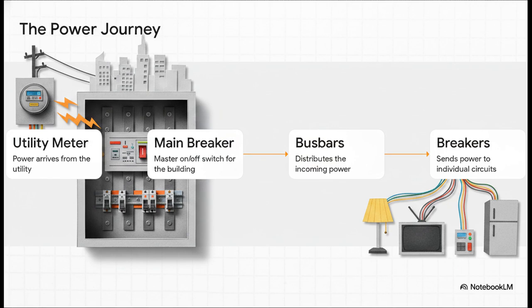To really demystify the panel, let's see how this builds. Imagine just stripping away the cover so we can trace the exact journey the electricity takes to get to your appliances. First, it arrives from the utility company, passes right through your electric meter, and enters the top of the panel enclosure. Once inside, boom, it hits the main breaker. Think of this as the master on and off switch for the entire building. From there, the power flows down onto these flat metal conductors called busbars, which run right down the center of the panel. Finally, the individual circuit breakers clip directly onto those busbars, drawing the power and sending it out to very specific circuits all over your home.